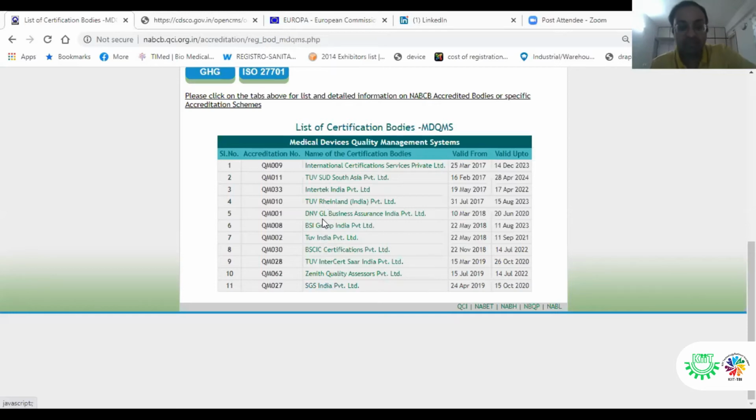These companies, SGS, BSI, DNV, TUV Rheinland, and TUV Sud, are also accredited by the European Commission for either CE certification and also for ISO 13485. So if you want to sell your product in European countries, you have to select only from these 5 notified bodies.